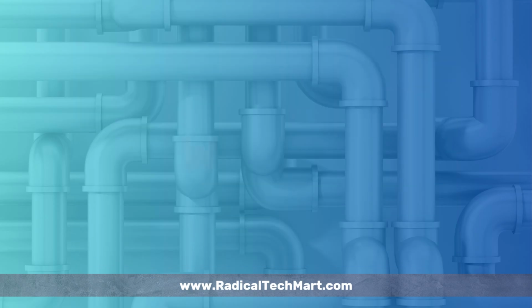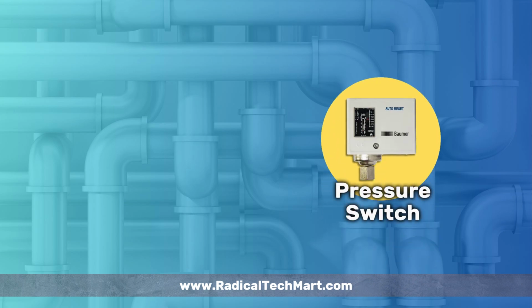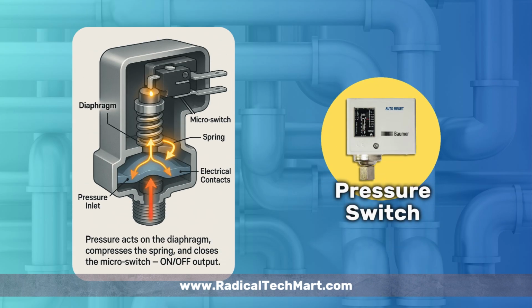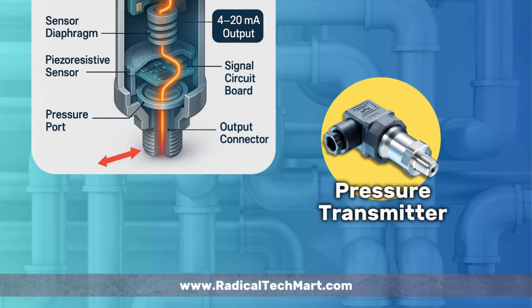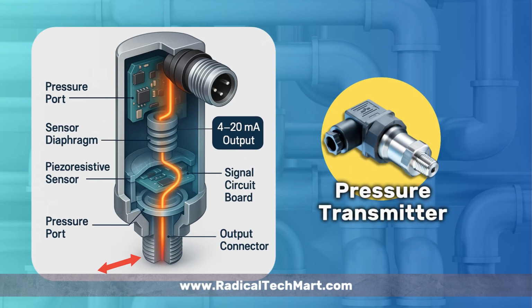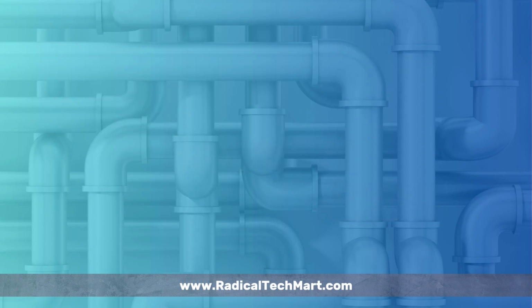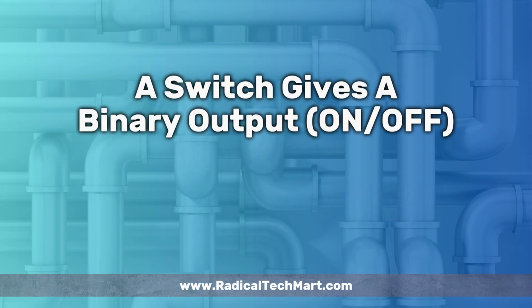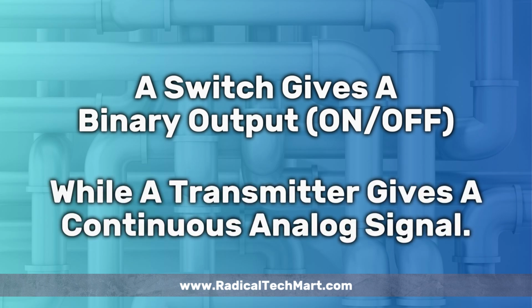on or off. In a pressure switch, system pressure acts on a diaphragm or piston, which pushes against a spring mechanism. When the set point is reached, the spring tension activates a microswitch, changing the electrical contact. It's purely mechanical. In a pressure transmitter, pressure acts on a sensor diaphragm, often piezoresistive, that converts the pressure into a proportional electrical signal.